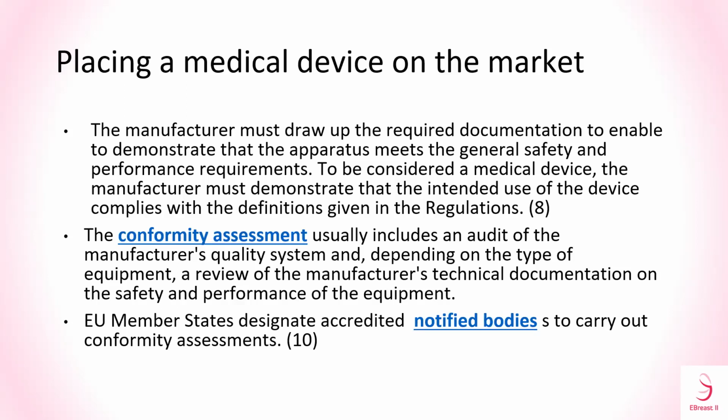The conformity assessment usually includes an audit of the manufacturer's quality system and, depending on the type of equipment, a review of the manufacturer's technical documentation on the safety and performance of the equipment. EU member states designate accredited, notified bodies to carry out conformity assessments.